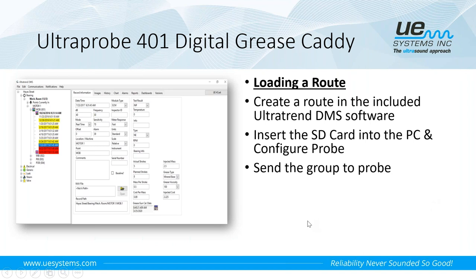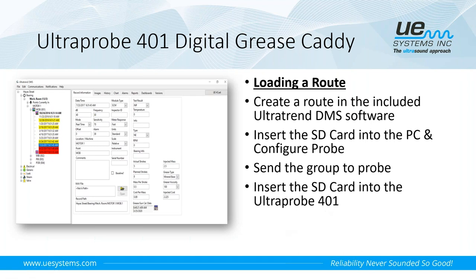Once we've done that, we're going to send group to probe. We simply highlight the route we just created, right click, and do send group to probe. From that point, we take the SD card out of our computer, insert it into the UltraProbe 401, power it on, and it will automatically load the route that we just created from the software.